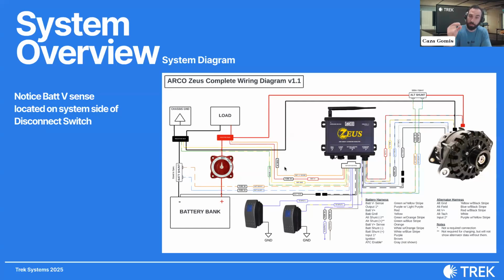You want to put that on the load side of the fuse. Again, in the event the fuse blows, it no longer senses voltage in the system, which tells the regulator to wind down the alternator. It says, hey, stop charging, because if the alternator keeps trying to push power and there's nowhere for it to go because the fuse is blown or the disconnect switch is off, that's bad news.